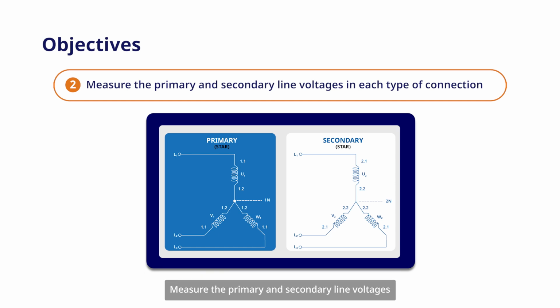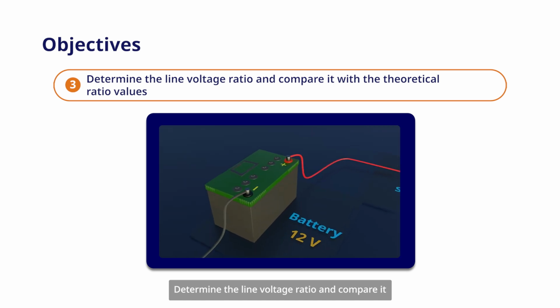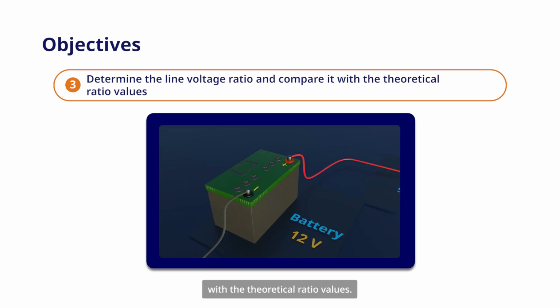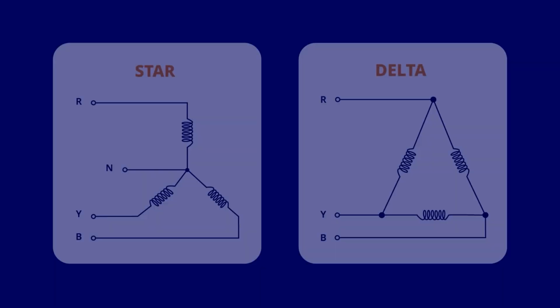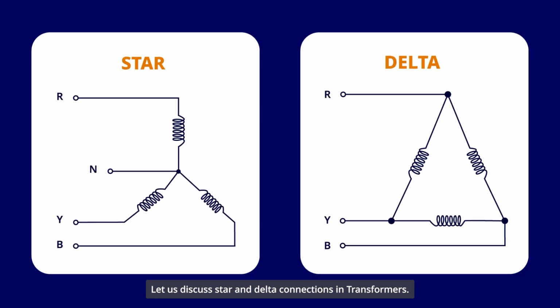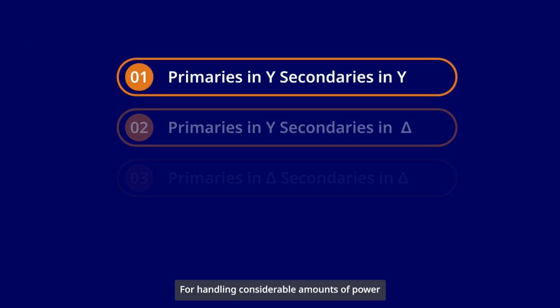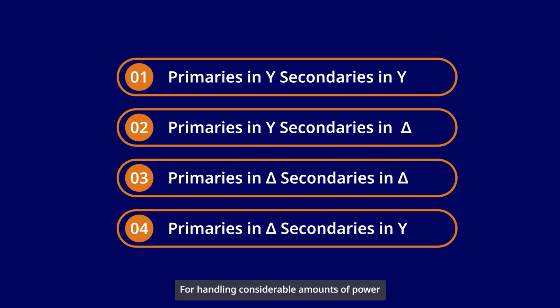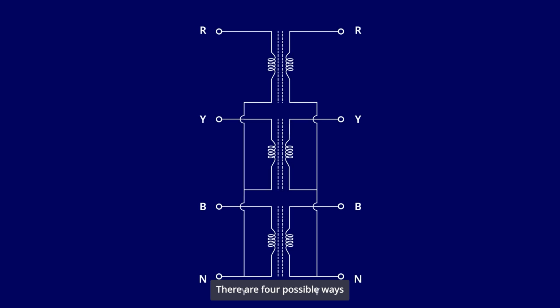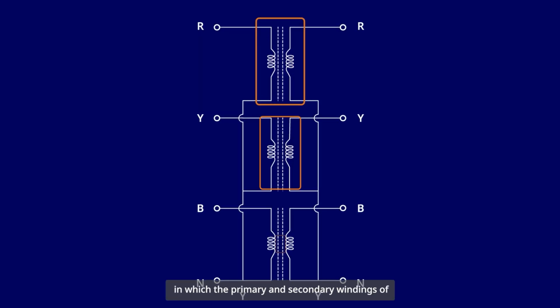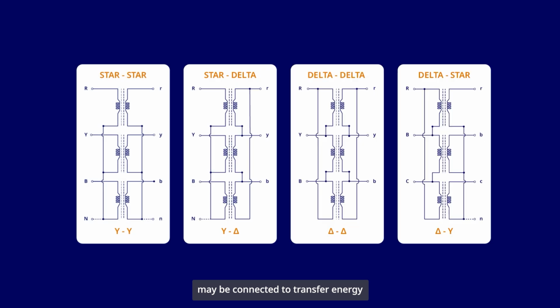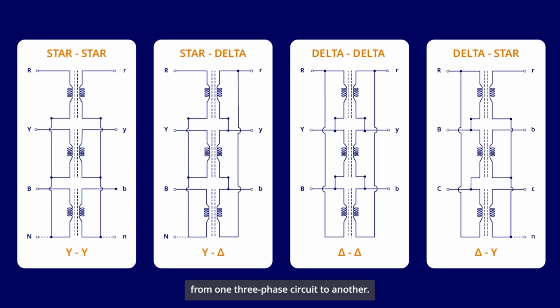Measure the primary and secondary line voltages in each type of connection. Determine the line voltage ratio and compare it with the theoretical ratio value. Let us discuss star and delta connections in transformers. For handling a considerable amount of power in three-phase voltages, various methods are available. There are four possible ways in which the primary and secondary windings of a group of three transformers may be connected to transfer energy from one three-phase circuit to another.